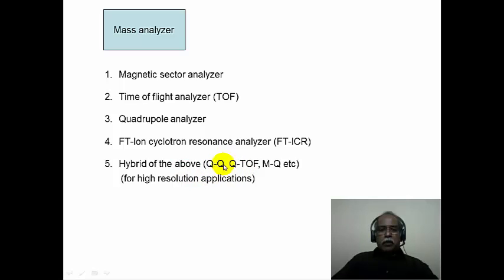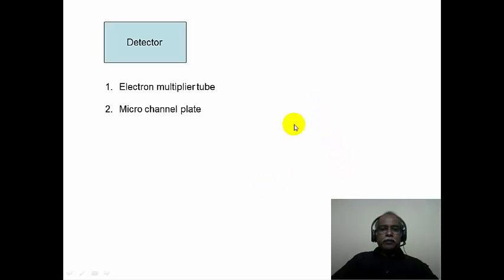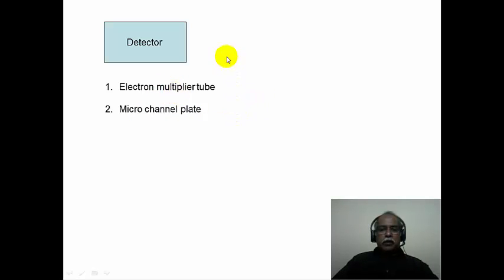For example, one can have a quadrupole-quadrupole (triple quadrupole) or a quadrupole time-of-flight analyzer. These combinations are used when high resolution is necessary. Detectors are essentially electron multiplier tubes or microchannel plates. The ions impinge on the electron multiplier tube, produce a current, and that current is registered as the signal corresponding to the mass spectrum.